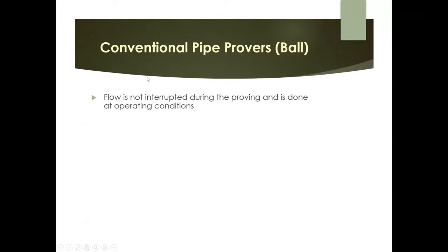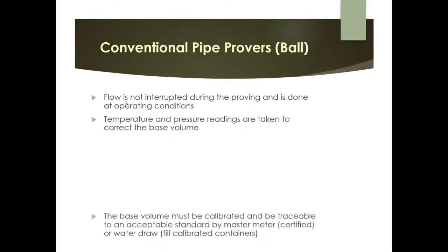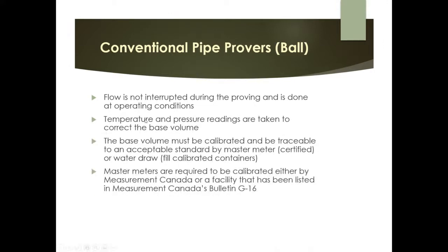For the conventional pipe prover: flow is not interrupted during proving and it is done at operating conditions. Temperature and pressure readings are taken to calculate the base volume. The base volume is calibrated and traceable to an acceptable standard, either by a certified master meter or water draw. Master meters must be calibrated by Measurement Canada or a facility listed in Measurement Canada's legislation.